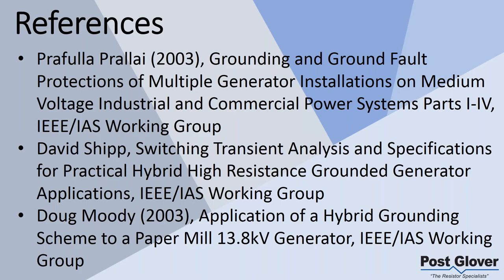Now with this one, however, there is a cost. In my personal opinion, high resistance ground is like a no-brainer to some degree. But hybrid grounding is basically application specific, and you really should do a cost benefit analysis. If you feel comfortable with it being fully protected and not taking a chance on a stator fault, let's say on a new generator, then I would say yes, go for it. But you have to look at the cost and you have to look at the benefit of it. So that's where I think there's a little more cost benefit analysis in this application.